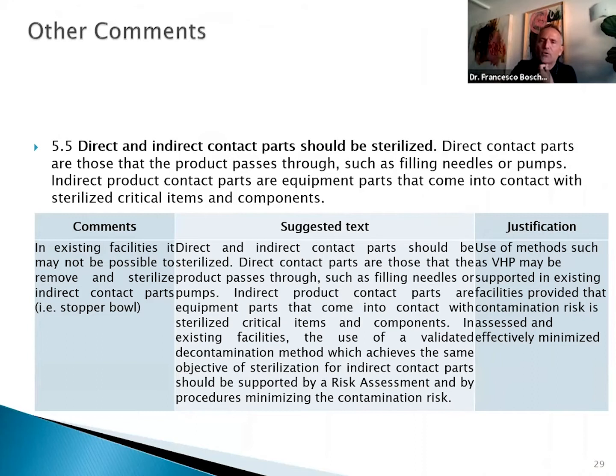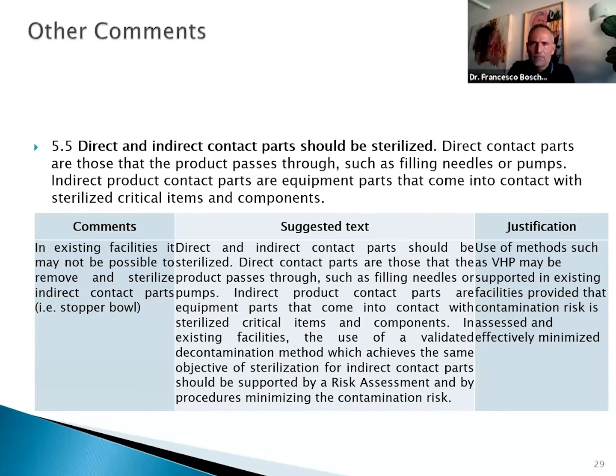As I was mentioning before, we had the possibility of commenting also on other parts of the annex. So we issued this comment on point 5.5, and specifically on the requirement that direct and indirect contact parts should be sterilized. Indirect contact parts are like the stopper bowls, stopper track, so surfaces in contact with primary components. In existing facilities, it may not be possible to remove and sterilize indirect contact parts. So for example, we have isolators, which generally are very well designed to protect the product, but in some cases in existing isolators, for example, the stopper bowl cannot be dismantled, so cannot be sterilized. So the use of validated methods such as VHP, we think, should be allowed, provided that they are supported by a contamination control strategy and by effective mitigation.